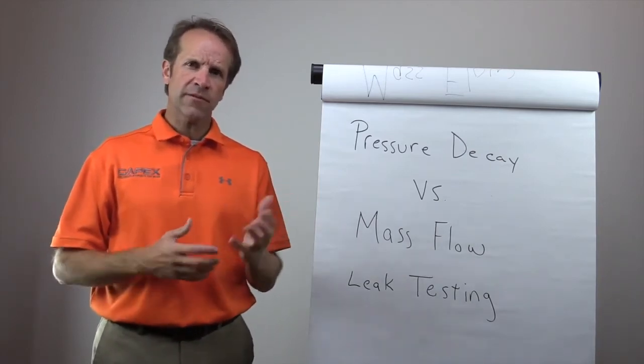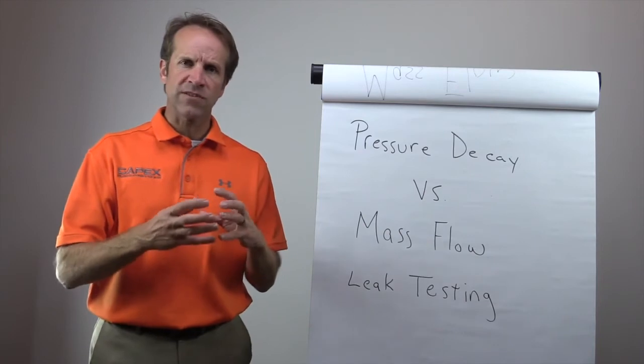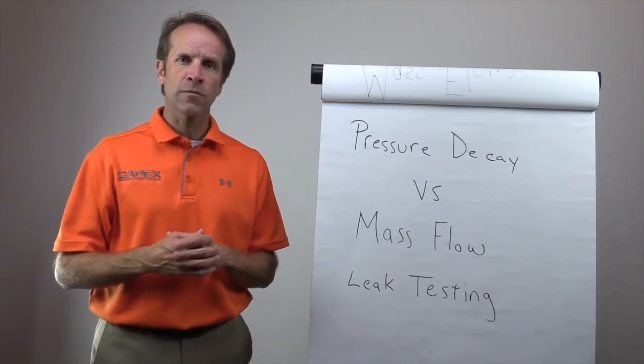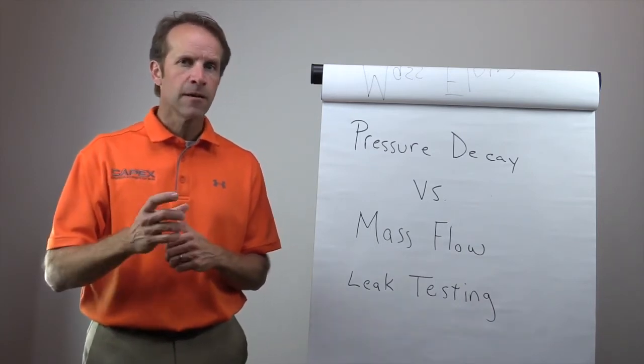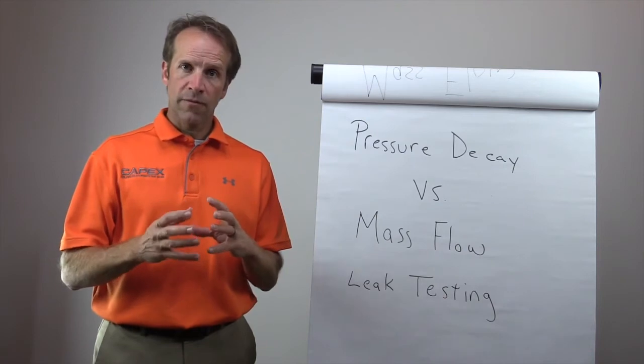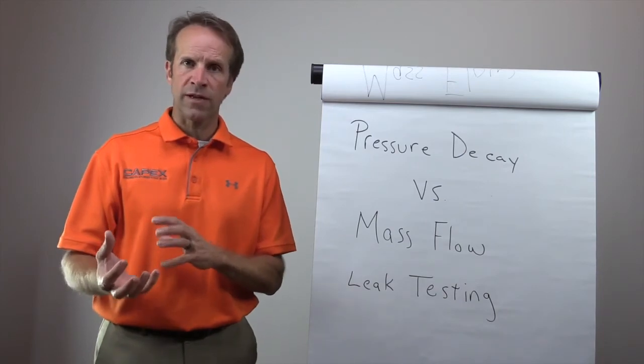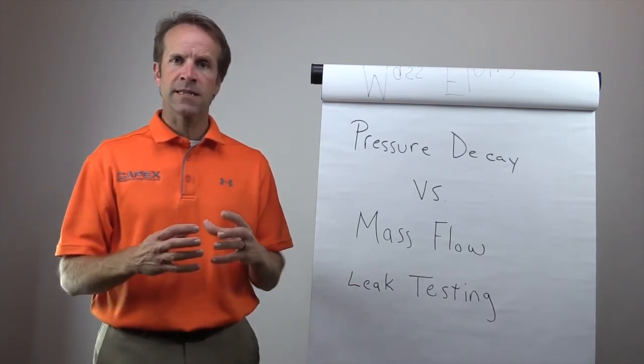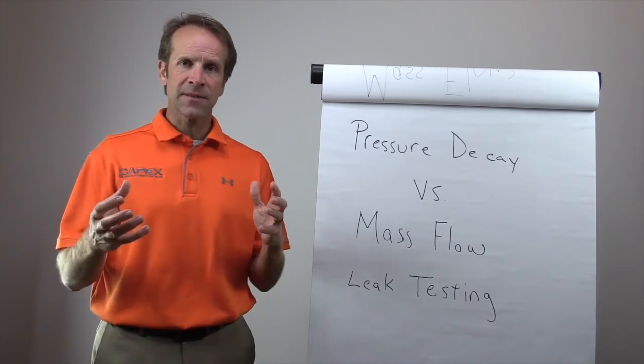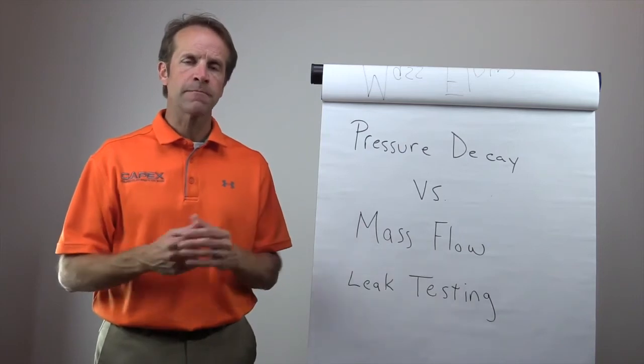So when to use pressure decay versus mass flow? Pressure decay is most commonly used for smaller applications. So if you have small applications, if you have very low leak rates, high speed applications are typically where we would utilize pressure decay leak testing. But again, remember, if you have significant part variation, so meaning the volume of the part that you're testing is going to vary significantly, you'll want to use a technology that's more forgiving. And pressure decay is not forgiving because it needs to be calibrated to a specific volume or the test really is not consistent from one part to the next if we're using the same reject criteria, but the volumes are varying.